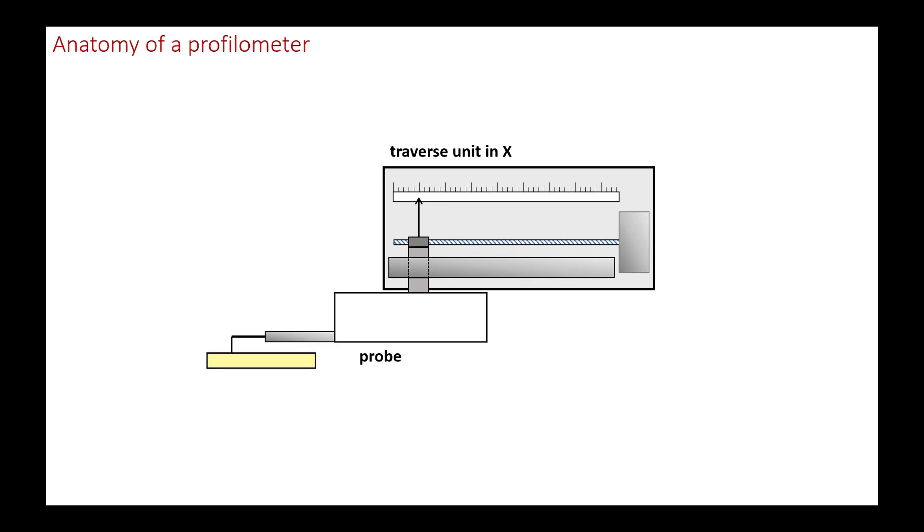More precisely, the sensor slides on a reference bar thanks to a drive screw driven by a motor. The bar serves as an internal straightness reference. It is an expensive element, ground with great precision, which often justifies the price of the profilometer.